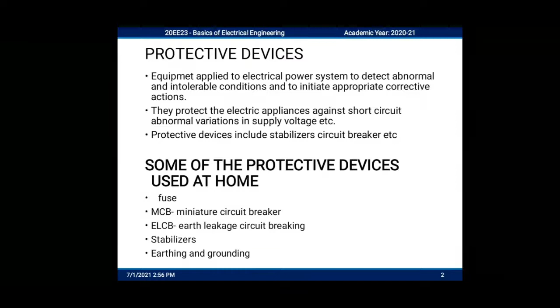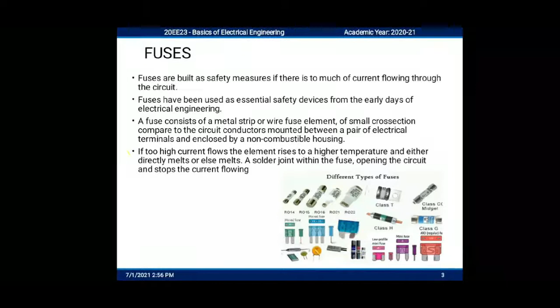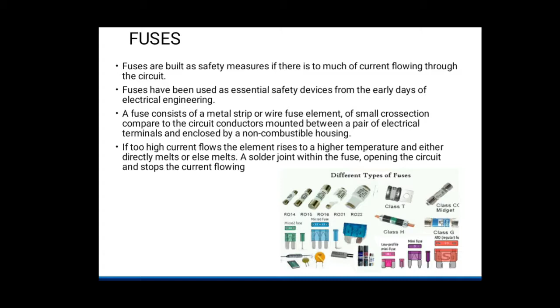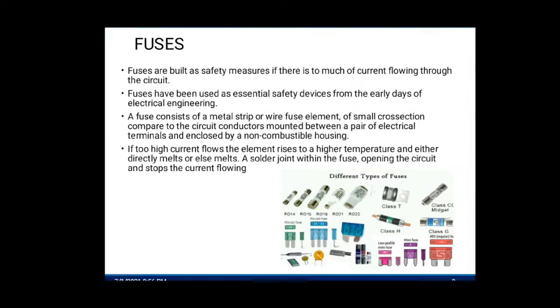Fuses are built for safety measures. If there is too much current flowing through the circuit, fuses have been used as essential safety devices from the early days of electrical engineering. A fuse consists of a metal strip or wire fuse element of small cross section compared to the circuit conductors, mounted between a pair of electrical terminals and enclosed by a non-combustible housing. If too high current flows, the element rises to a higher temperature and either directly melts or else melts a solder joint within the fuse, opening the circuit and stopping the current flowing. Some different types of fuse photos.